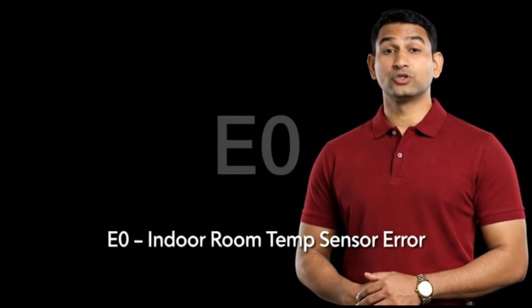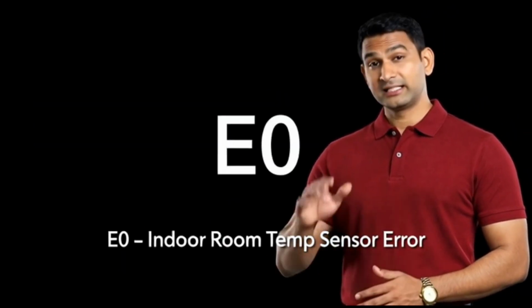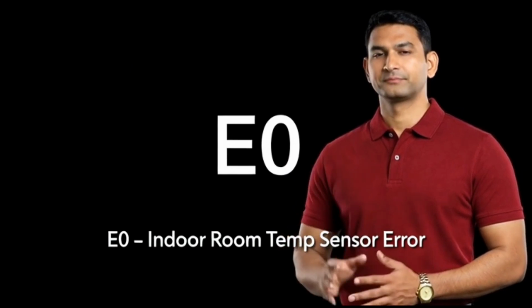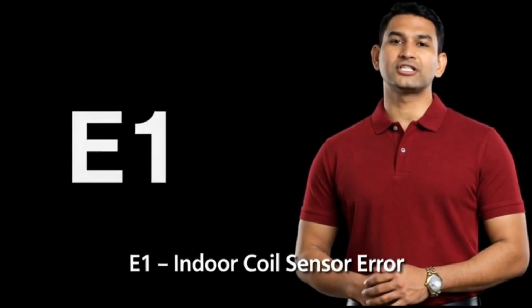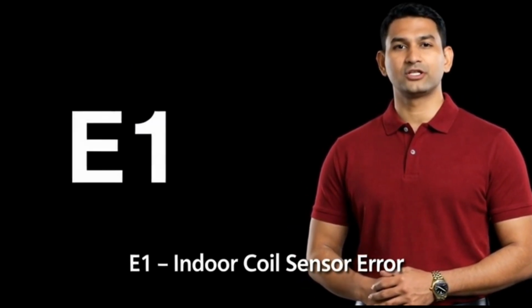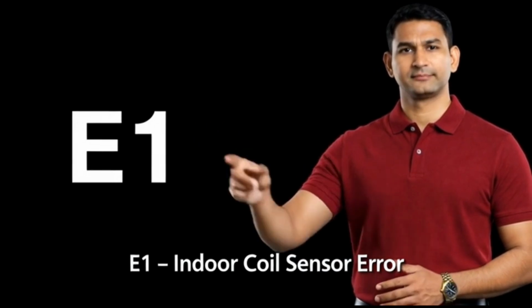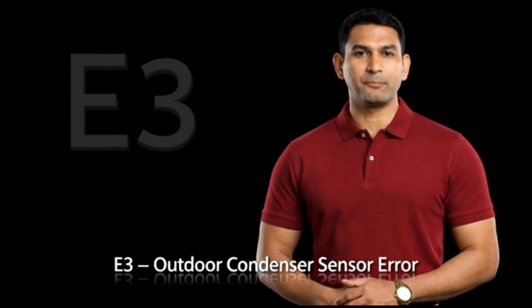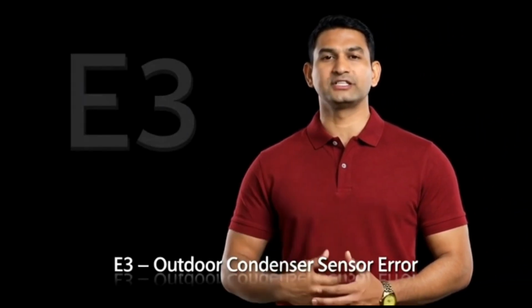E0 error indicates indoor room temperature sensor failure. AC cannot detect room temperature properly. E1 error shows the indoor evaporator coil sensor is faulty, cooling may be affected. E2 error means the outdoor ambient temperature sensor is not working properly. E3 error indicates a problem with the outdoor condenser coil sensor.